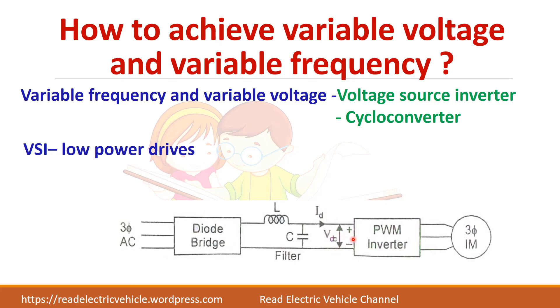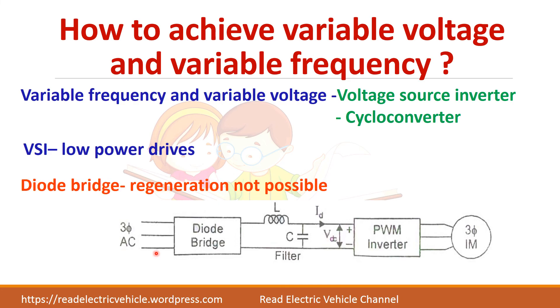The three-phase AC supply is converted to DC by the diode bridge rectifier, then filtered to remove ripples, and that ripple-free output is given as input to the inverter. When using a diode bridge, you are not able to feed power back to the supply — that is, regeneration will not be possible. If you use a thyristor bridge instead, power can be sent from the motor back to the supply, making regeneration possible.